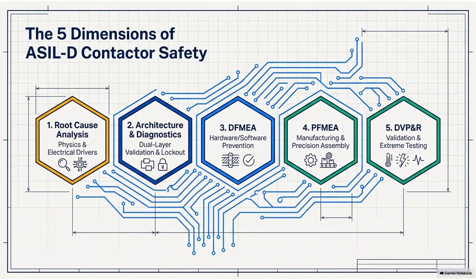But unfortunately, even a matrix of silver and tungsten has thermodynamic limits. Right. When that DC arc strikes, the localized thousands of degrees of heat instantly exceed the melting point of the silver within that alloy matrix. Oh, wow, so it just liquefies. Literally, the surface of the contact liquefies. You have boiling liquid metal pooling on both sides of the microscopic gap.